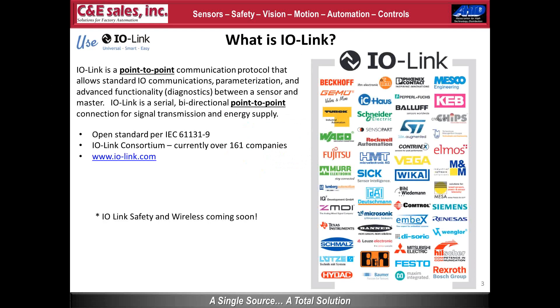IO-Link is not a network — it's a point-to-point communication link. In addition to signal transmission, we also transfer energy or power supply for the sensor or actuator. IO-Link conforms to the standard IEC 61131-9, and the IO-Link consortium manages the development and maintenance of the protocol. Currently, over 161 companies are part of the consortium. For more information, visit IO-Link.com.